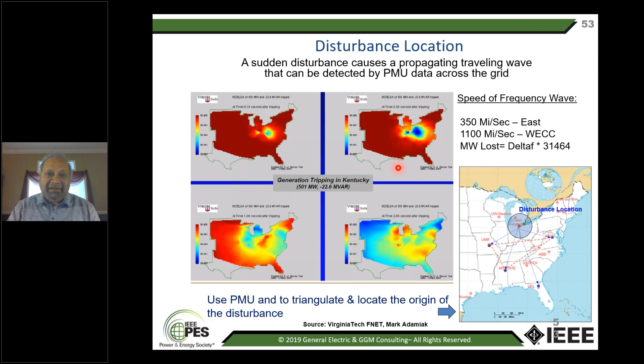Also islanding, you can look at situations where you've suddenly islanded. I know this doesn't happen often, but with the traditional EMS it would take many minutes to determine where you islanded and which lines are affected. With PMUs, within a matter of a second, you know exactly where the island is. This is coherent, and this is the second island. So it's a much faster visualization or awareness of happenings on the grid.